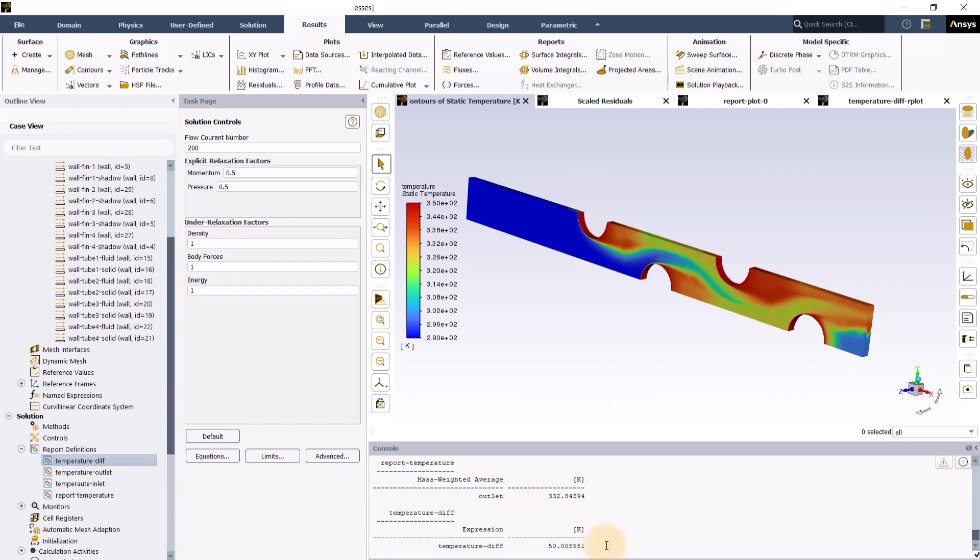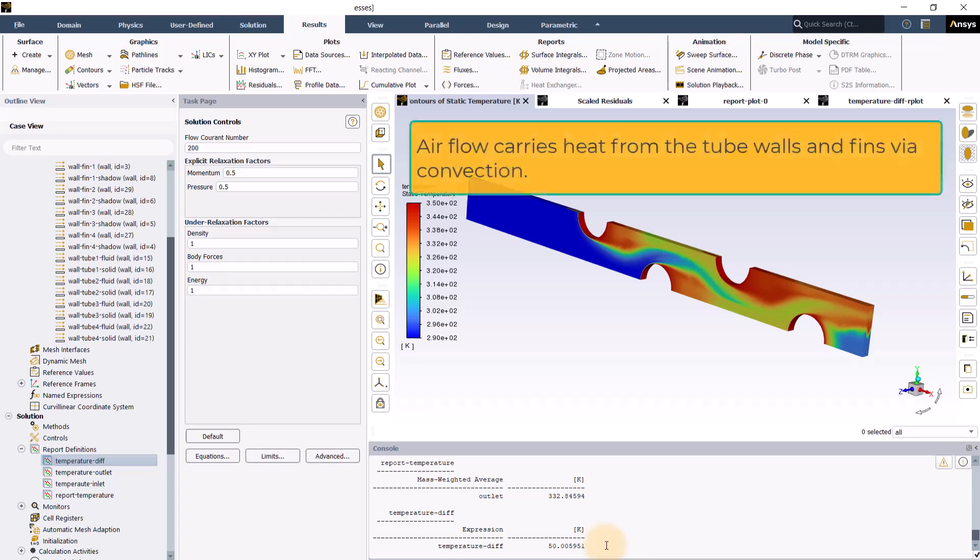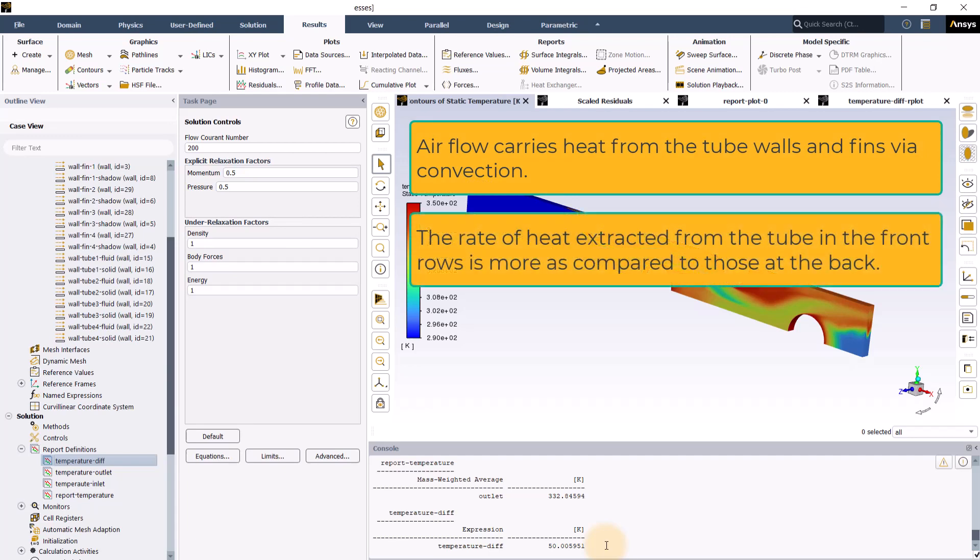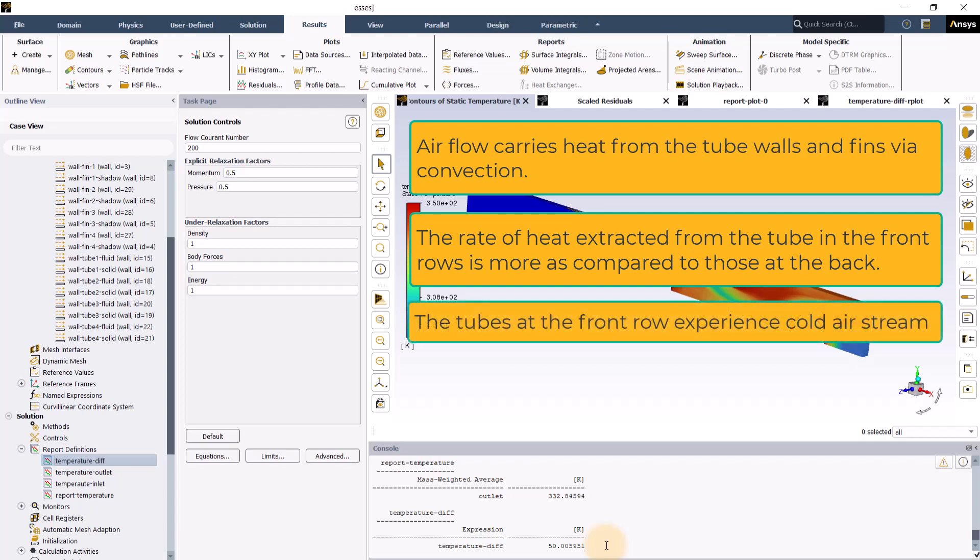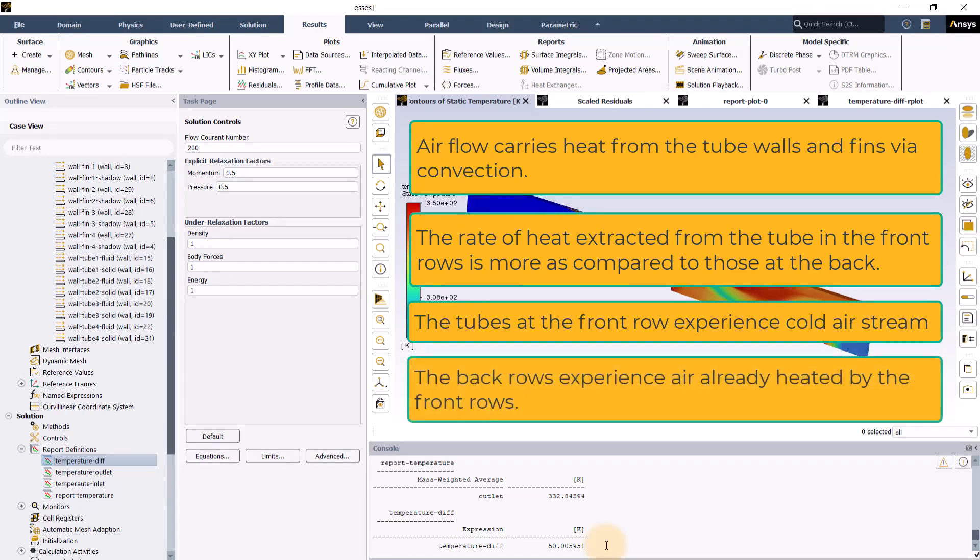Therefore, from the temperature contour plot, it can be understood that the airflow carries heat from the tube walls and fins via convection. Also, the rate of heat extracted from the tube in the front rows is more as compared to those at the back. This is because the tubes at the front row experience cold air stream while the back rows experience air already heated by the front rows.